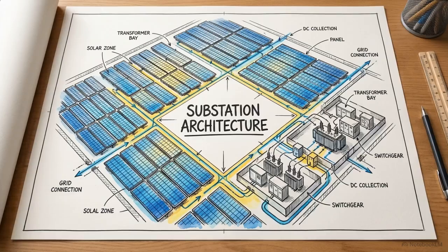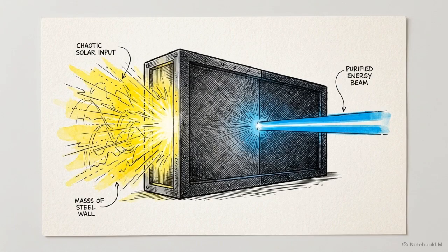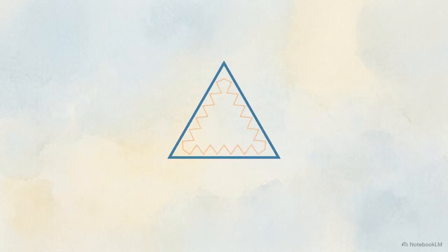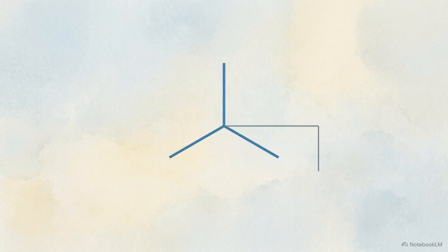For large solar plants, engineers rely on a specific configuration known as the Dyn11 transformer. It functions as a protective firewall between the raw solar farm and the polished national grid. The delta connection traps erratic triplen harmonics so they never reach the grid. The star connection provides a grounded neutral to balance uneven electrical loads caused by cloud shading. Finally, Dyn11 dictates a 30-degree phase shift, perfectly aligning output with utility distribution architectures.